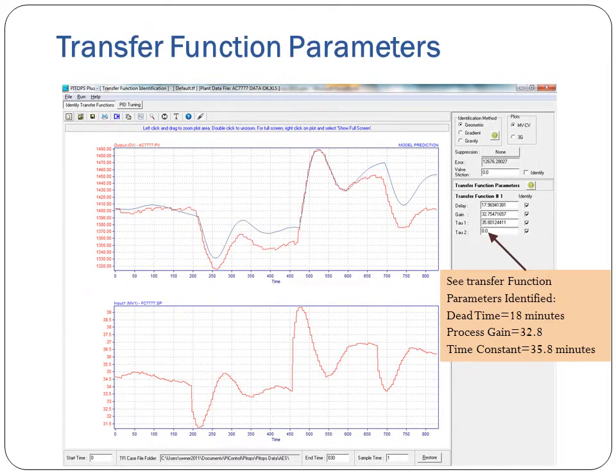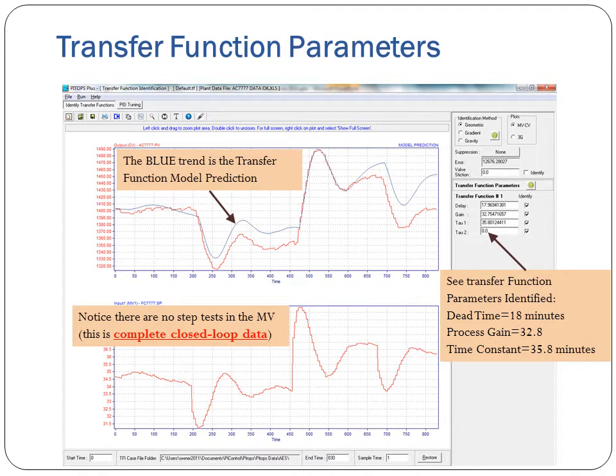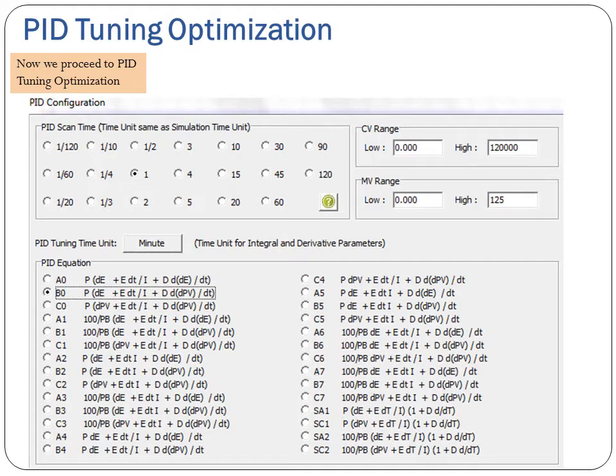See the transfer function parameters identified: dead time equals 18 minutes, process gain equals 32.8, and time constant equals 35.8 minutes. The blue trend is the transfer function model prediction. Notice there are no step tests in the MV — this is complete closed-loop data. Now we proceed to PID tuning optimization.